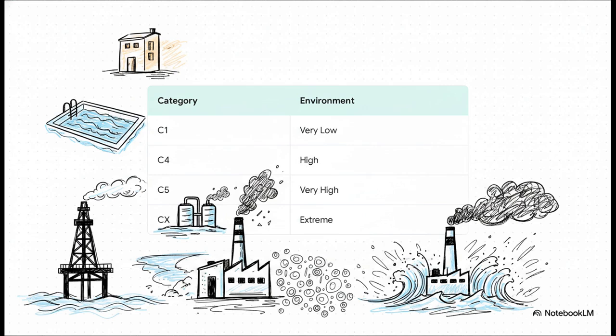We start at C1, which is very low corrosivity. We're talking heated indoor spaces, offices, schools, basically zero pollution. Skip ahead to C4, and now we're hitting high corrosivity. This is your indoor swimming pools or chemical plants. C5 is very high. This is heavy industrial areas, coastal zones getting blasted with chlorides, or anywhere dealing with super high condensation frequencies. And finally, CX, extreme. This is the wild stuff. Offshore rigs taking constant salt spray, places where condensation is basically permanent. And listen, whatever category you're in, it 100% dictates the materials you absolutely have to use for your equipment.